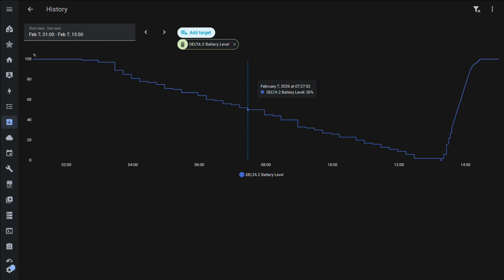Here you can see the midpoint of discharge. Exactly 5 hours have passed, level 50%. 10 hours from the moment of outage, charge level 2%, the station shuts down. After that the level practically stabilizes until power is restored and charging begins.